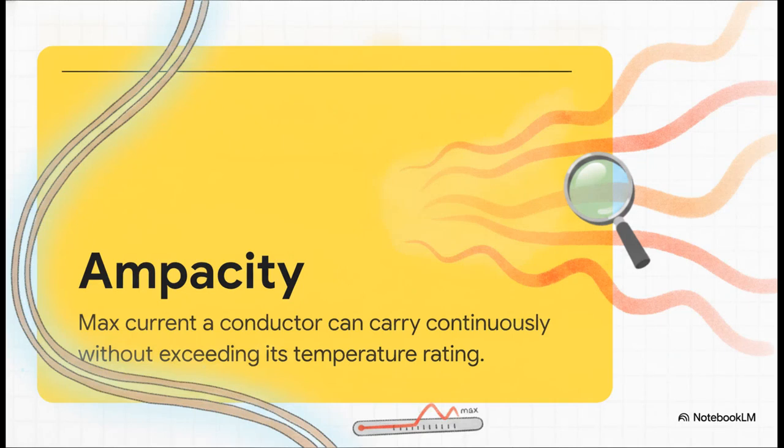Now, think of ampacity as our ultimate target number. It is basically the lifeblood of our conductor sizing. When we start pitting environmental heat penalties against those continuous load penalties we just talked about, ampacity is the exact rating we are desperately trying not to exceed.